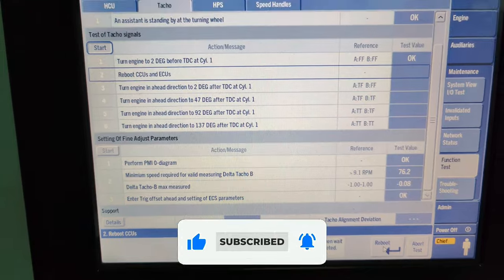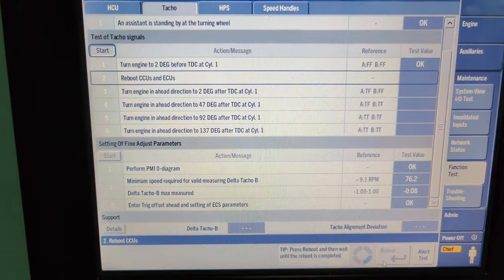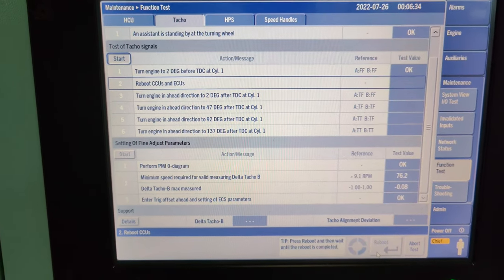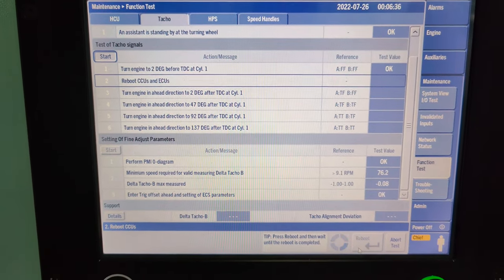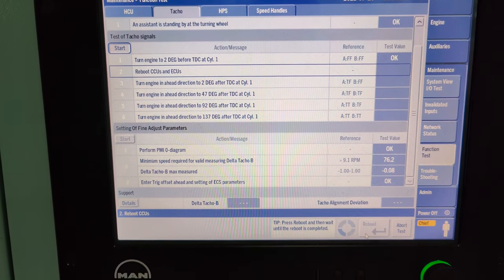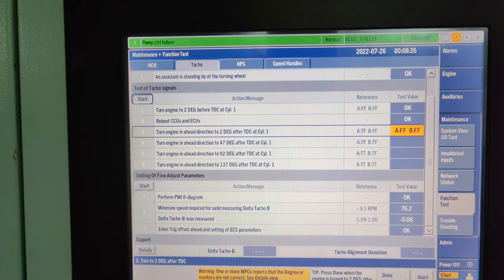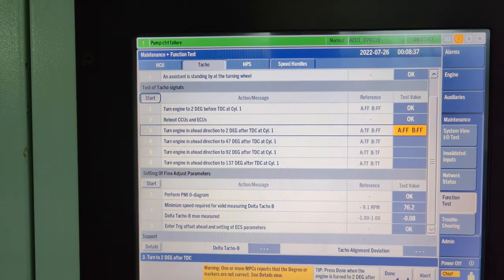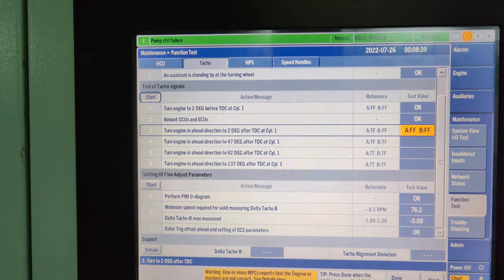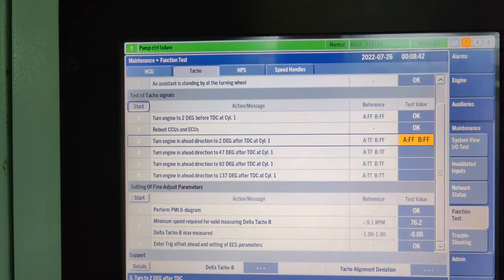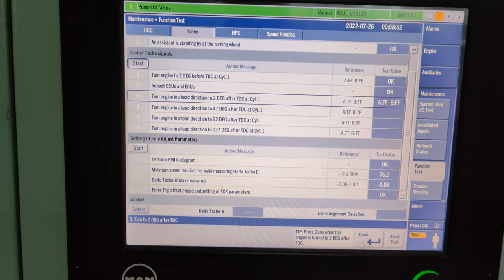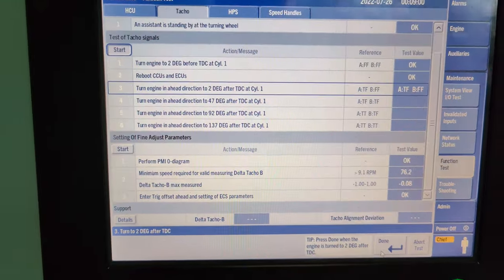Then press done and proceed to the second instruction, which is to reboot the CCUs and ECUs. Carefully follow the instructions as per the tips displayed at the bottom of the screen. Once the rebooting of the MPCs is done, turn the crank 2 degrees in the ahead direction after TDC at cylinder number 1. Upon achieving this crankshaft position, the test value changes from yellow to blue background. Then press done.